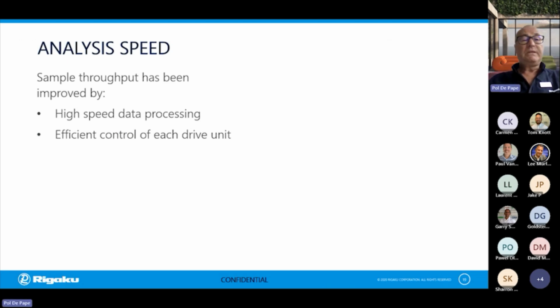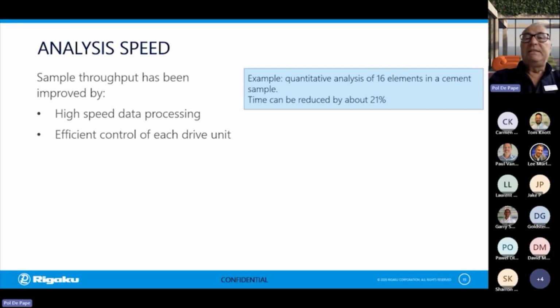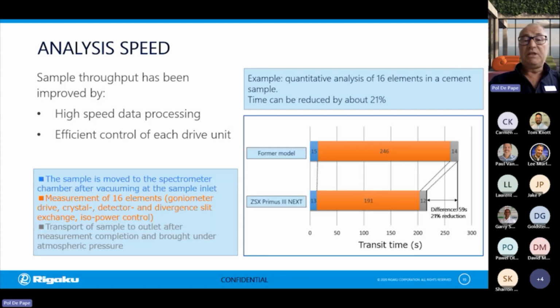Analysis speed. So we have improved the sample throughput by high speed data processing, but also by efficient control of each drive unit. So what does this mean? We have one example here, 16 elements in a cement sample, where we could observe a reduced measurement time of about 20 to 21%. So in our former model, we can see here the time that we needed to bring the sample in the measurement position, the sample measurement time, and then to bring the sample back out of the spectrometer. So now with our ZSX Primus 3 Next, we can do this in about 20% less time. So we can see reduced measurement time. And this is, of course, very important. This is just because we speed up the drive units, the crystal moving, the detector moving, and so on.